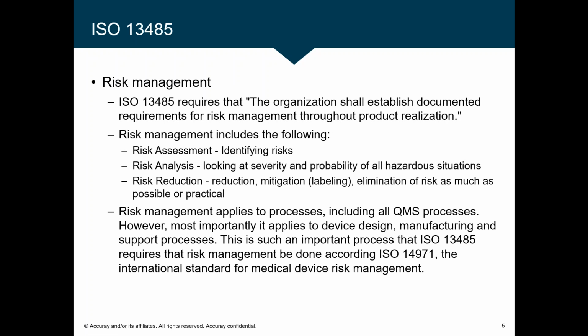13485 also talks about risk management. It requires that an organization establish a documented requirement for risk management. And actually called out within the standard is that you use your labeling to mitigate risk.